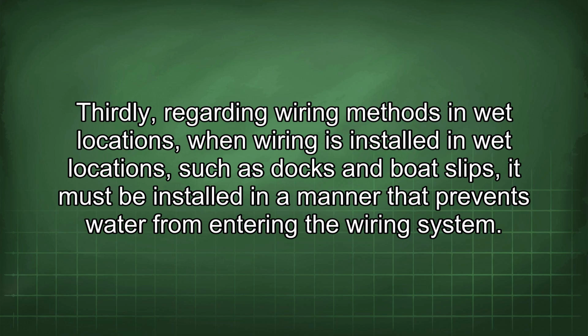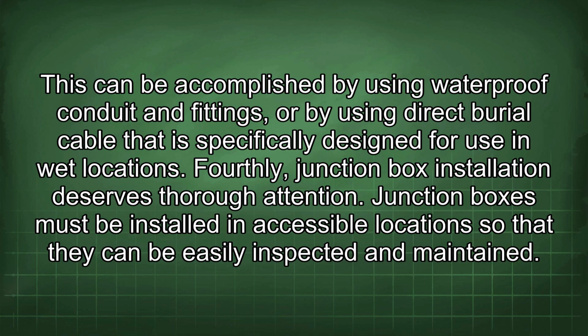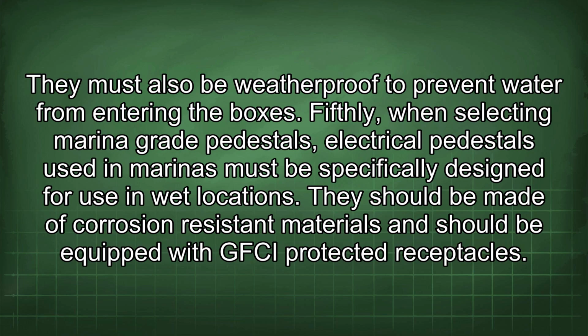Thirdly, regarding wiring methods in wet locations, when wiring is installed in wet locations, such as docks and boat slips, it must be installed in a manner that prevents water from entering the wiring system. This can be accomplished by using waterproof conduit and fittings, or by using direct burial cable that is specifically designed for use in wet locations. Fourthly, junction box installation deserves thorough attention. Junction boxes must be installed in accessible locations so that they can be easily inspected and maintained. They must also be weatherproof to prevent water from entering the boxes.